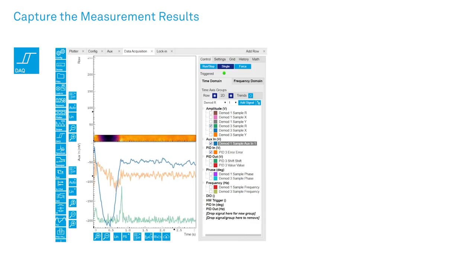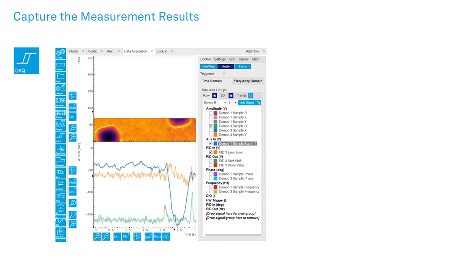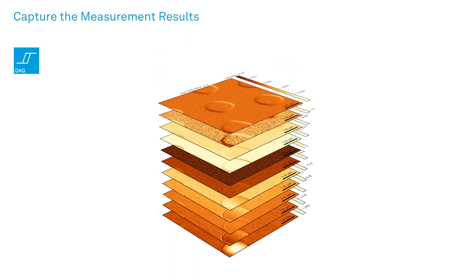Capturing the measurement results and building up images synchronized with the AFM scan is possible with the LabOne Data Acquisition module. As a result, we have an entire stack of images each carrying unique information about the sample. And most important, they are perfectly aligned since they were all recorded simultaneously in one run.